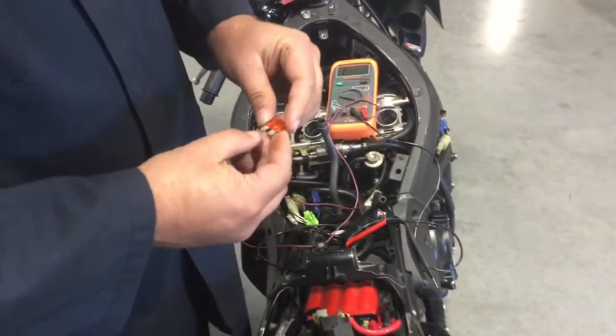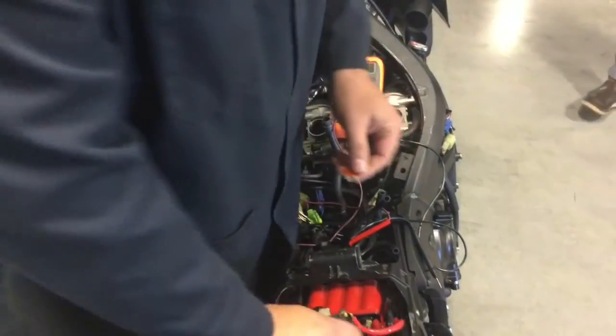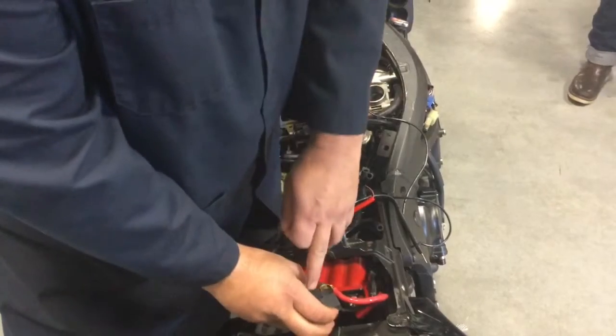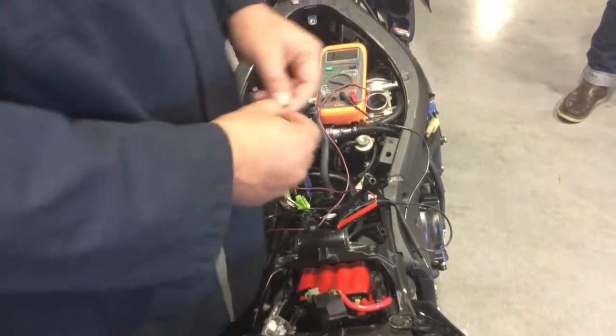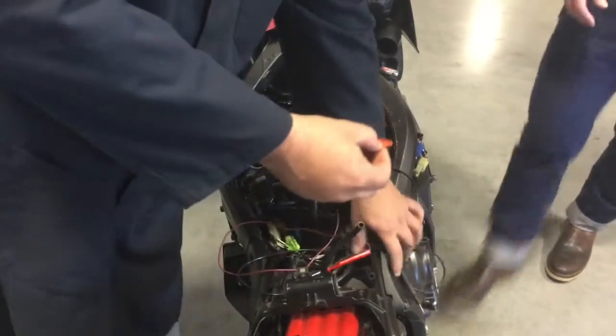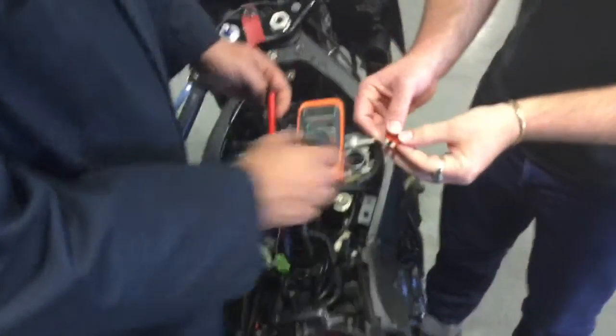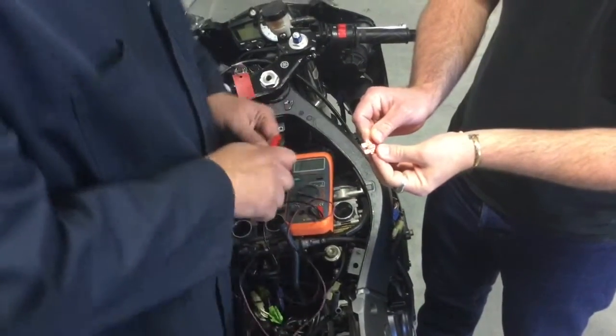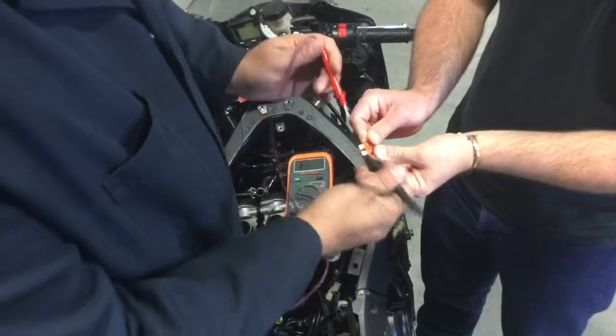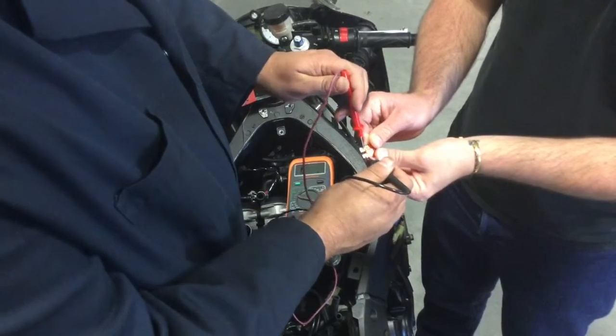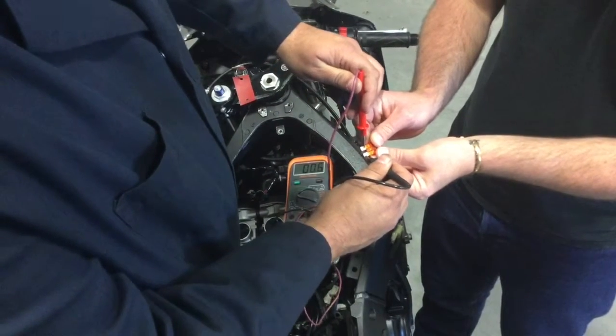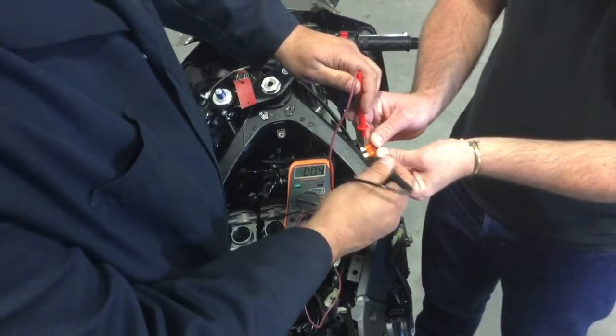Test the main fuse, which is that 40 amp fuse. Look at it, make sure it's not blown, make sure there's no corrosion. Also look at the plug, make sure there's no corrosion there too. I'm going to do the same test we did on the little 15 amp. Make sure your meter's set on ohms, take one probe, touch one side to the other. And then we should get a 0.5, 0.6, we're good.